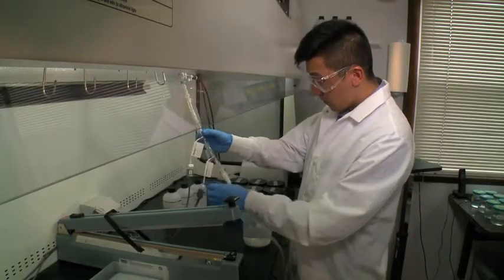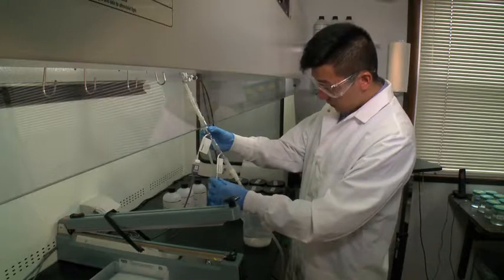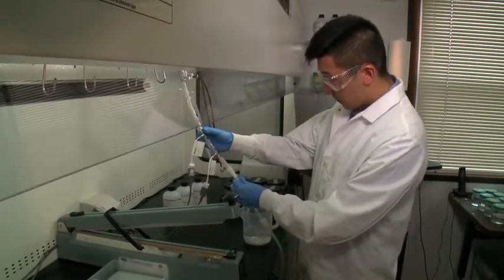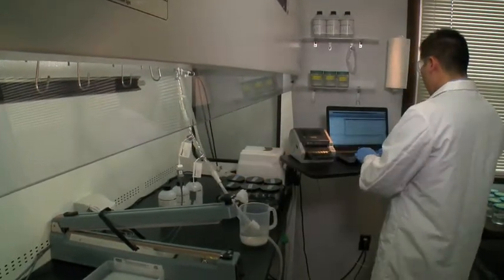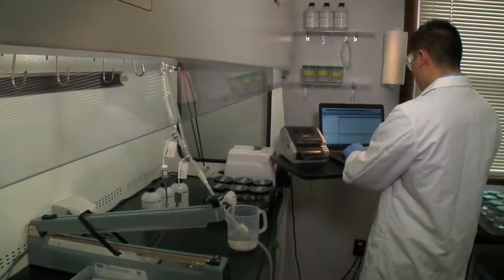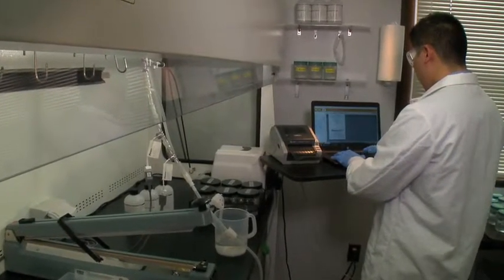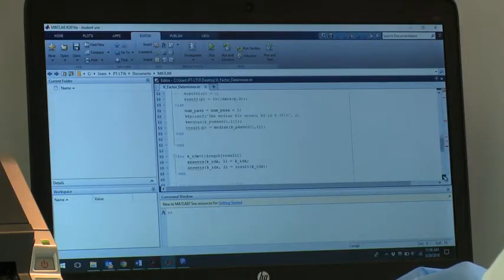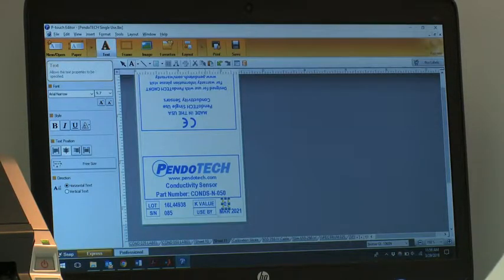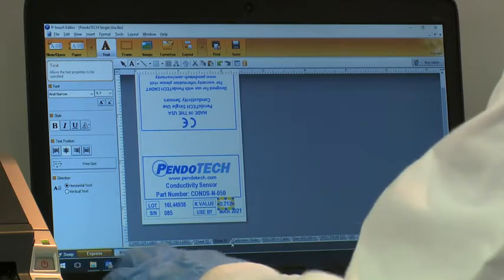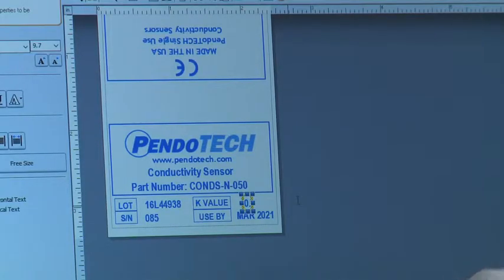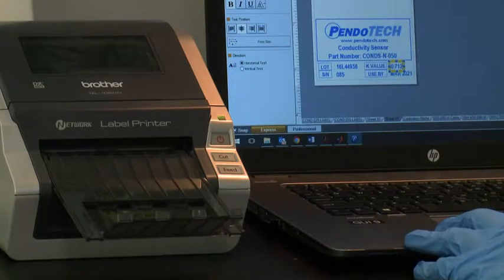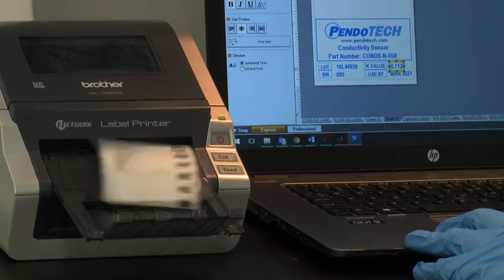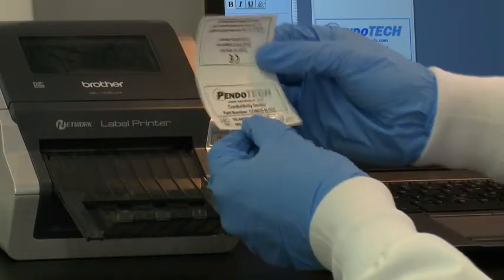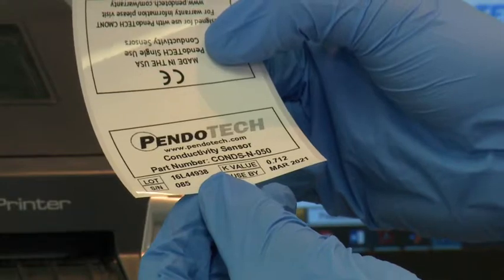The completed sensor's built-in accuracy is accomplished by determination of the sensor's cell constant, or K. This is accomplished by exposure of the sensor to a range of conductivity (NIST) traceable standards. Then, the data is entered into a mathematical model to determine the optimal K value. The model also determines, with this new K value, that the sensor is within specification or the sensor is rejected. The individual K value is printed with the sensor label that also contains the sensor part number, lot number, and serial number.